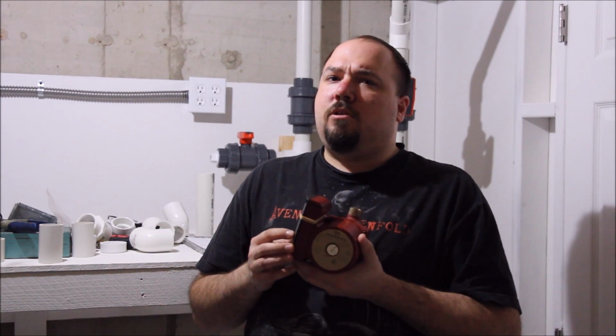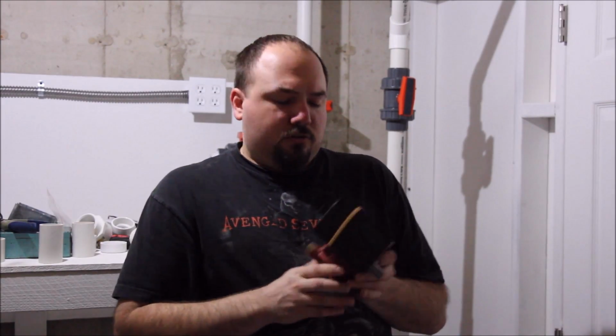Now, you might think since it's a hot water tank, water comes out one end and goes back in the other, that could be considered closed. But technically that's an open system because new water is coming into the hot water tank and water is leaving it. That's why I switched to a bronze pump. In fact, reading the forum posts, the gentleman at VLDesign.com who did this also discovered his cast iron pump had a lot of rust and corrosion, so he changed it out to bronze. That's why I went with bronze too.